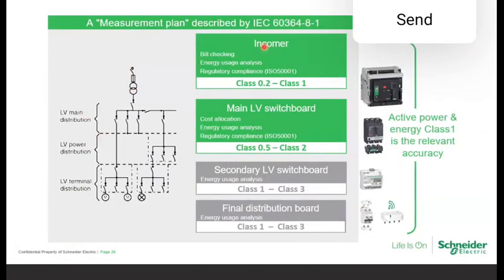So you can see from incomer to the final distribution level, I can use the incomer with the MTZ ACB. So no need of external CTs, no need of external meter and accessories. In MCCBs, we also have the NSX range, which will give you the metering parameters. Then you can go for the PowerTag in the final distribution, which is again the first wireless energy sensor in the world, which gives you the class 1 energy accuracy, and sits on the top or bottom of the MCB, and it will give you the energy values remotely through Zigbee communication. So this is IEC 60364-8.